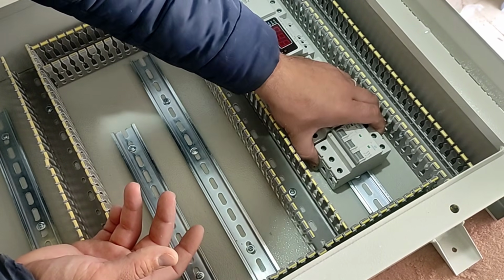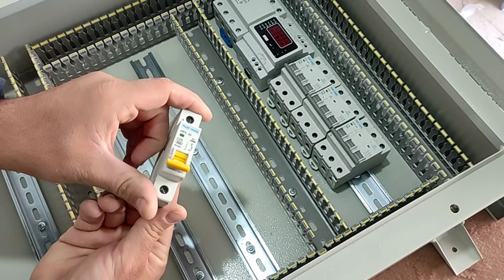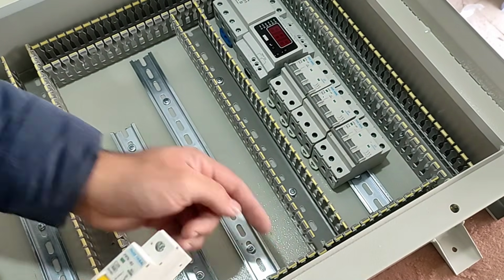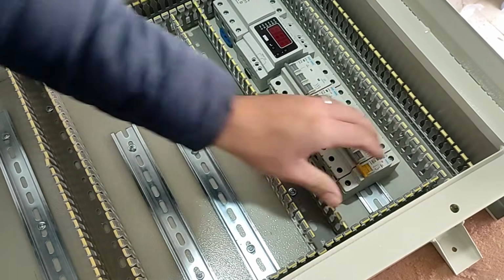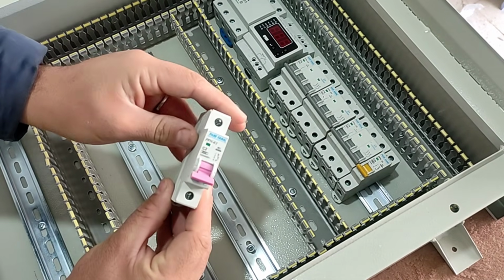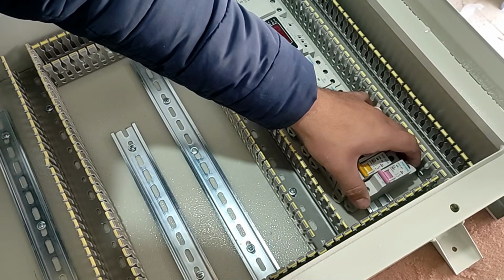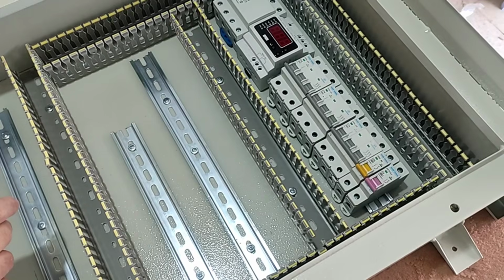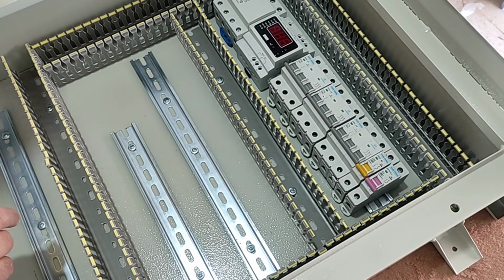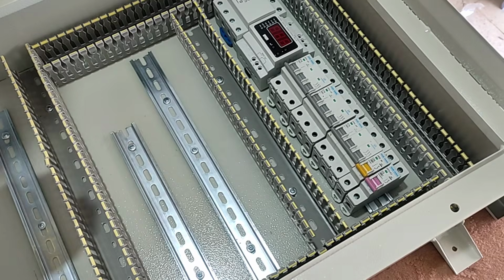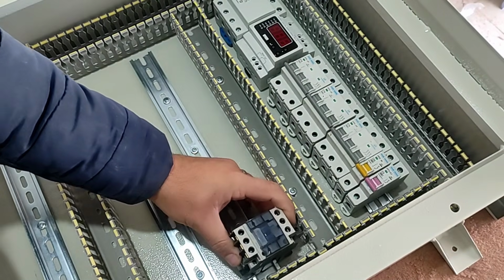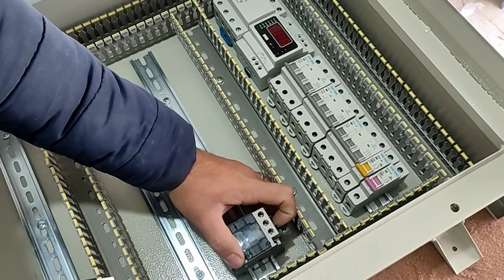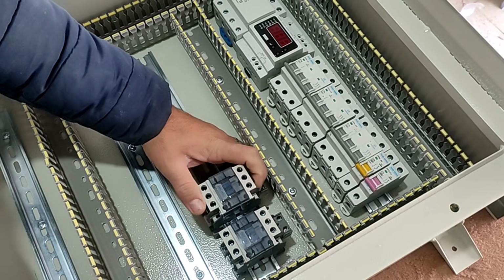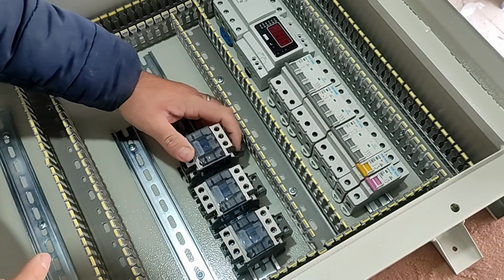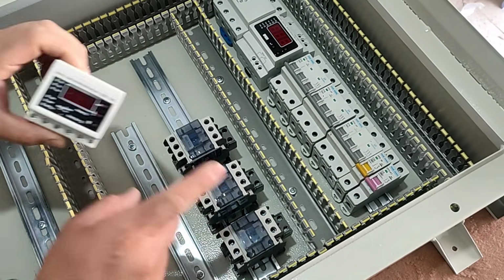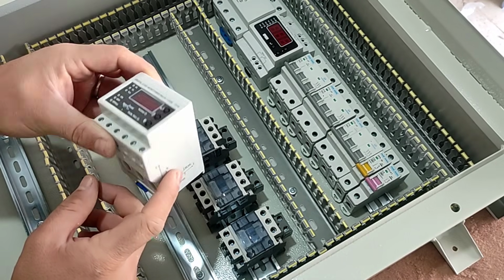Also, this electrical panel includes a single-phase output that is installed on the body of the electrical panel with a single-phase outlet. We use a single-phase 2 ampere switch to connect and disconnect the command circuit. Also, each three-phase output needs a contactor, which we install. We use a current controller relay to protect each three-phase electric motor.